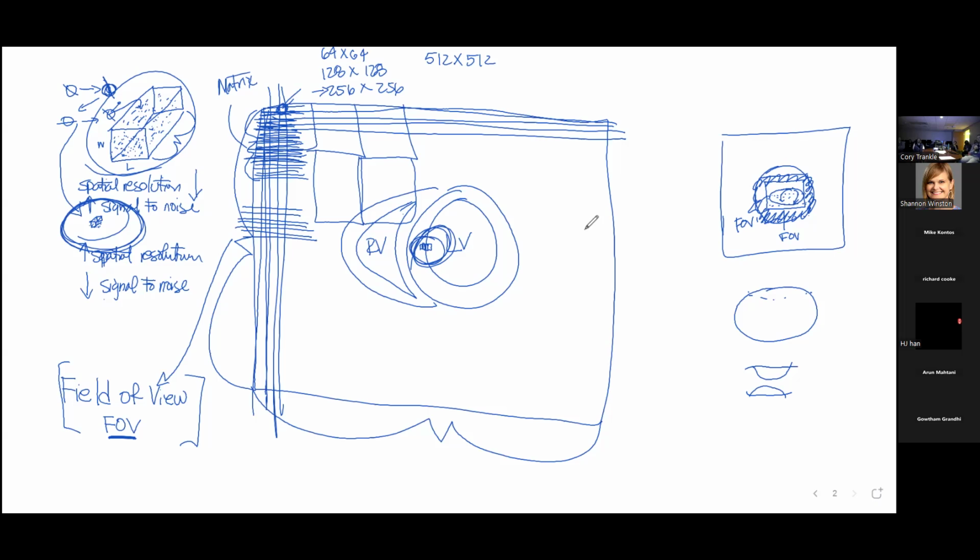In fact, when this magnet was put in, we spent probably 3 or 4 months, none of you were here, setting up what the fields of view and the spatial resolutions would be. So you didn't have to do that every time you show up. You've got a good rough estimate, but you're going to have to make adjustments, okay? Because you're imaging protons. If you make these things so small, you're not going to have enough signal emanated from those things to put the picture together.